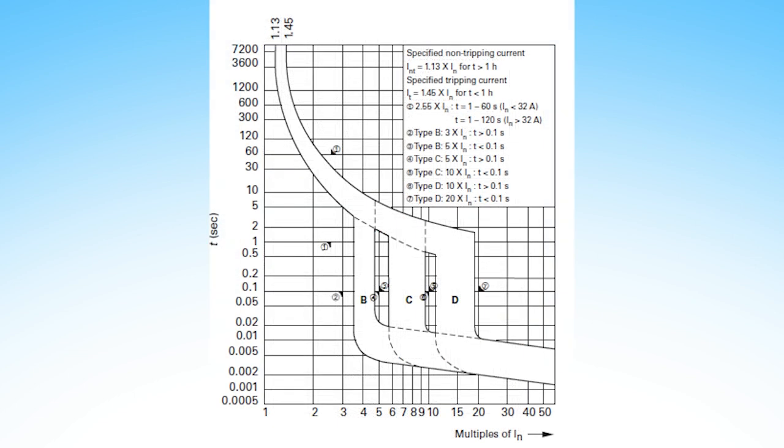This curve has three different curves in one chart because the breakers for this chart are available in B, C, or D curves. Let's look at the range of a typical motor inrush. This is usually six to eight times the FLA.